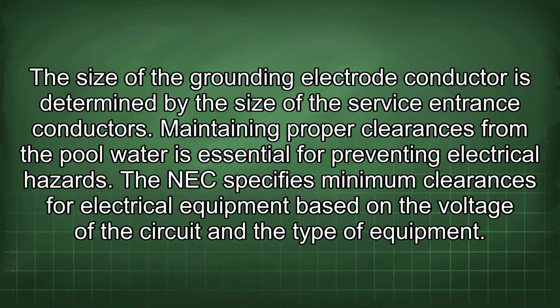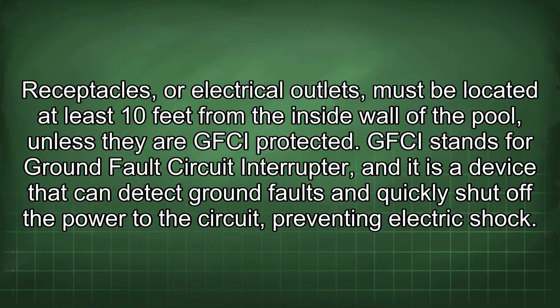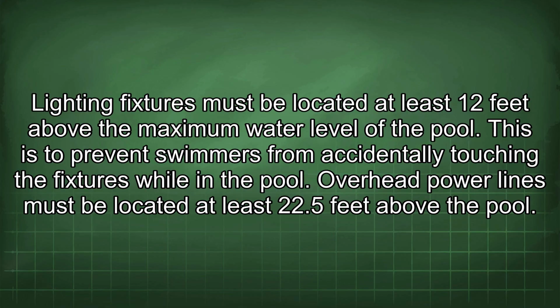Maintaining proper clearances from the pool water is essential for preventing electrical hazards. The NEC specifies minimum clearances for electrical equipment based on the voltage of the circuit and the type of equipment. Receptacles, or electrical outlets, must be located at least 10 feet from the inside wall of the pool unless they are GFCI protected. GFCI stands for Ground Fault Circuit Interrupter, and it is a device that can detect ground faults and quickly shut off the power to the circuit, preventing electric shock. Lighting fixtures must be located at least 12 feet above the maximum water level of the pool. This is to prevent swimmers from accidentally touching the fixtures while in the pool. Overhead power lines must be located at least 22.5 feet above the pool.